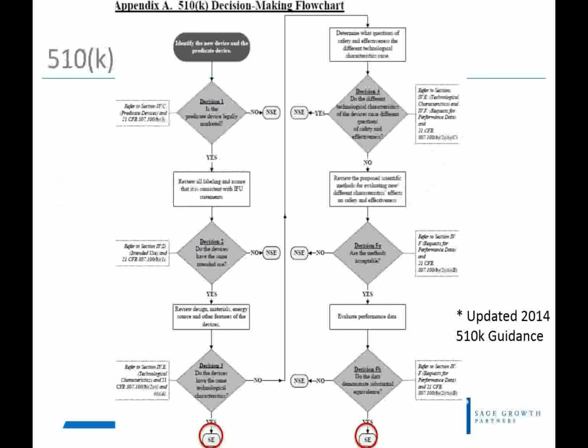It's really critical to work with experts that can help you ask the proper questions so you get the most out of it. A 510K, this is how you get your Class 2 device cleared and on the market. And you have to show something called substantial equivalence. So you find another device that has already been cleared through 510K. That becomes what's called your predicate device. And you show that you are substantially equivalent, which means you're either better, equal, or worse by a small margin that is not significant.